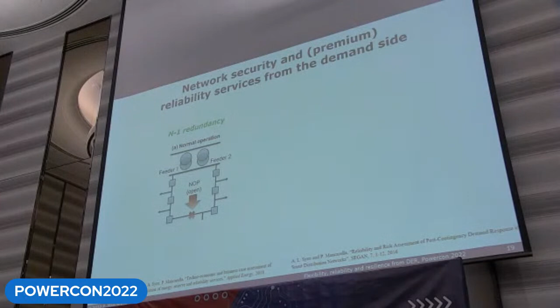This is a typical N-1 design distribution feeder. You have two feeders, basically oversized - double the size needed - because in case there's a fault in the network, you want to be able to close that normally open point and backfeed from the substation. For this worst case condition, that network can only be utilized at 50% capacity, so you build two networks. Now, how often does that extreme fault actually happen?